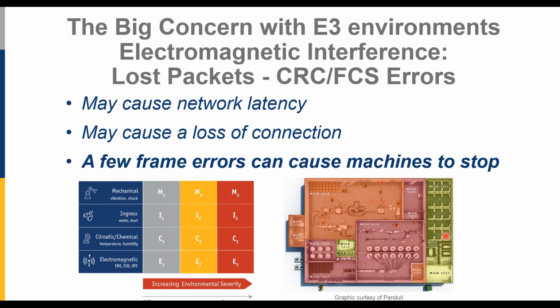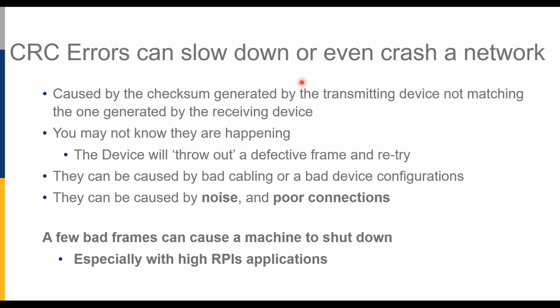What we worry about with that electromagnetic interference are CRC and FCS errors. What is a cyclical redundancy check or frame checksum error? Technically, it's caused by the checksum generated by the transmitting device not matching the one generated by the receiving device. We're transmitting ons and offs, and if an off gets interference on the wire while being transmitted and turns into an on, that frame is corrupted. The frame can't be read and is thrown out as a physical layer error.